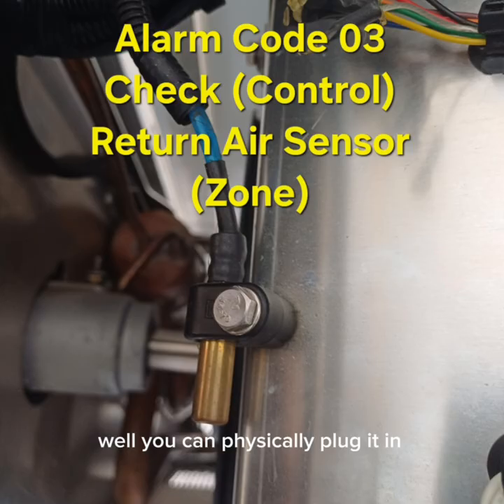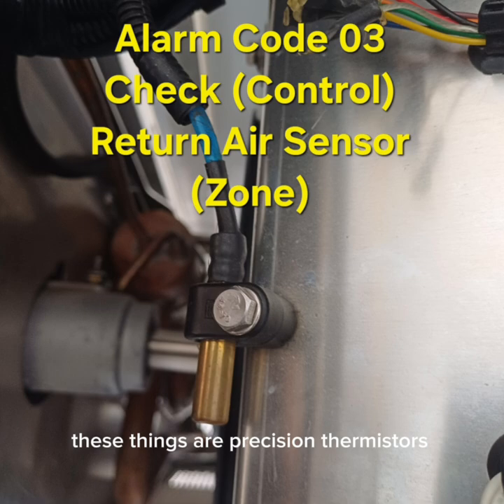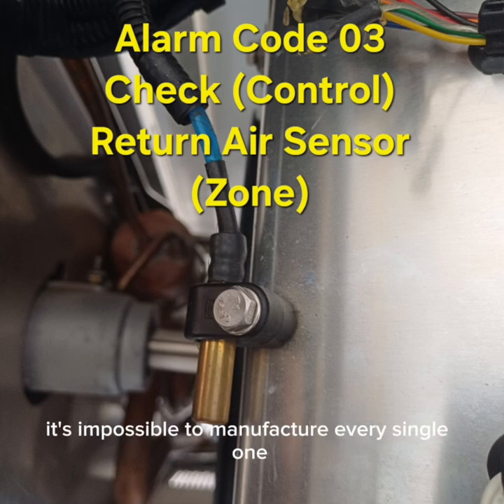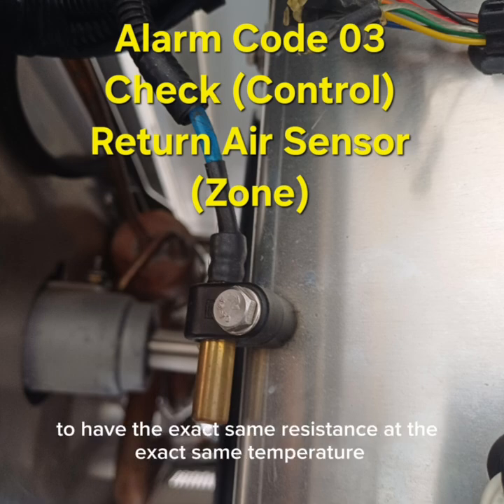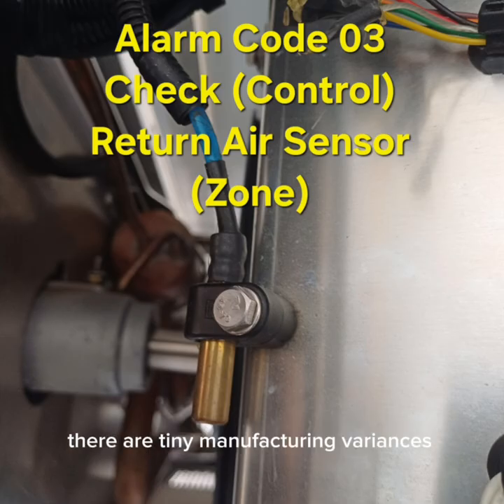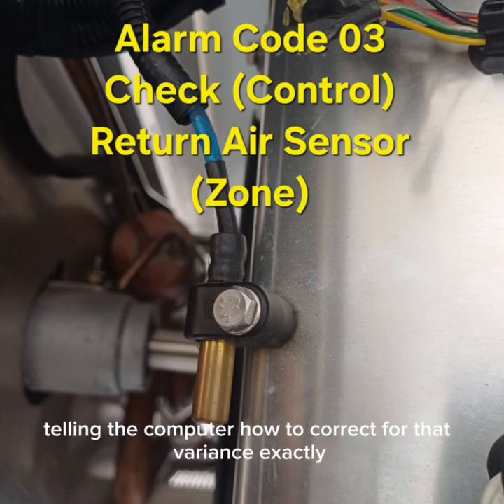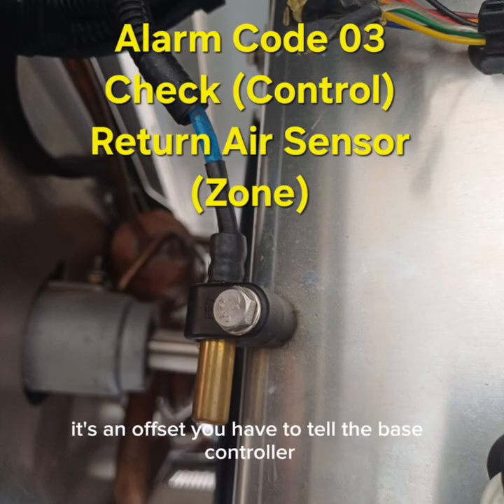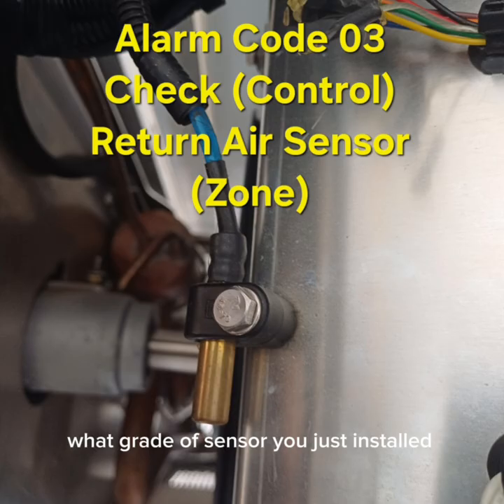Well, you can physically plug it in, but the computer's not going to like it. Or rather, it won't understand it. These things are precision thermistors. It's impossible to manufacture every single one to have the exact same resistance at the exact same temperature. There are tiny manufacturing variances. So the grade is basically telling the computer how to correct for that variance. Exactly. It's an offset. You have to tell the base controller what grade of sensor you just installed. It's like calibrating a scale.